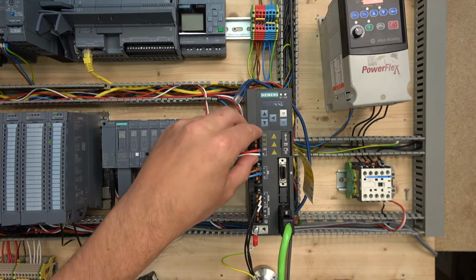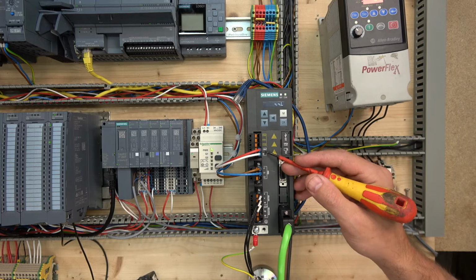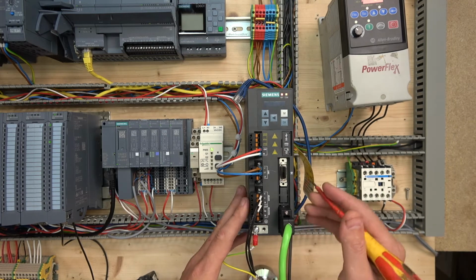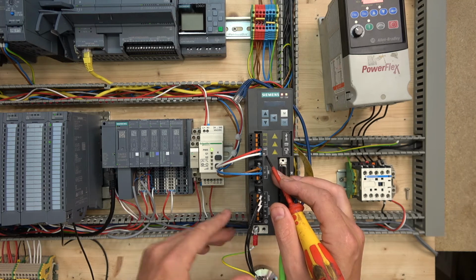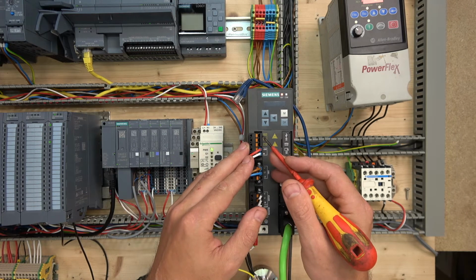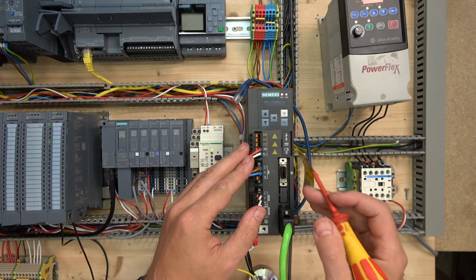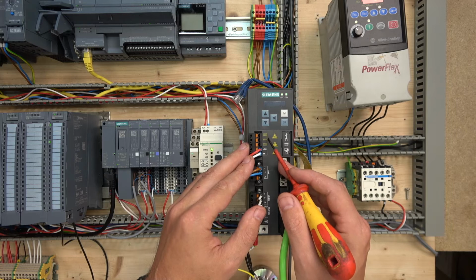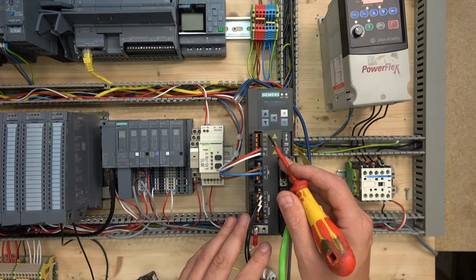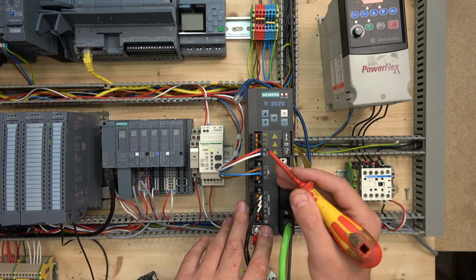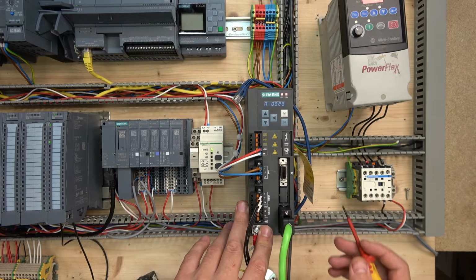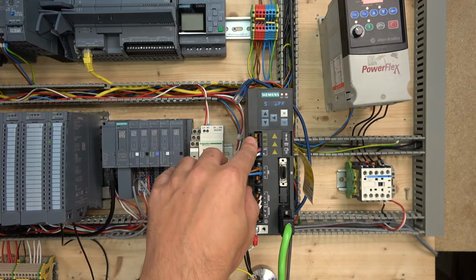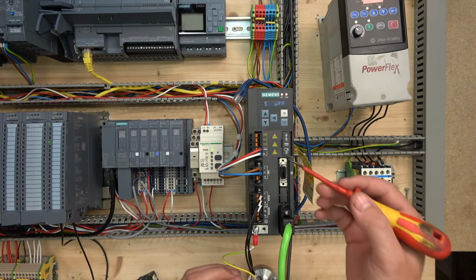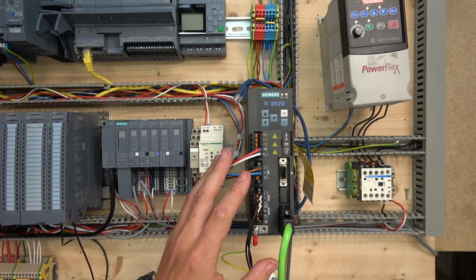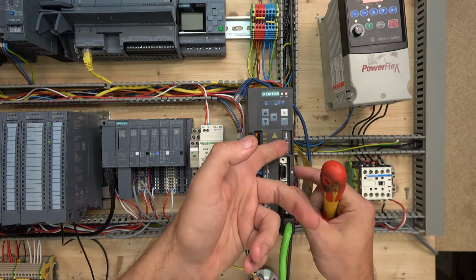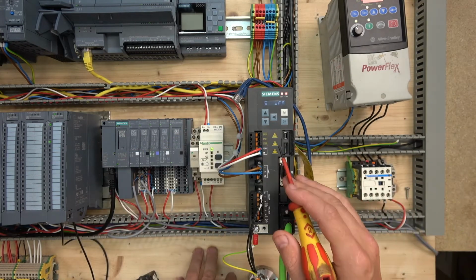From there on, we plug that on. We have a 24 volt supply for the controls, and as you can see, the drive has come on. It's 24 plus and minus coming from the DC power supply. Also, we have a link in here which links out STO, safe torque off, something like that. Basically, if these are open, and some cables are going to it and they're open, the drive will not run. So if you are using these, and you have a problem and the drive doesn't run, the first thing to check is to make sure that's there. After that, you have a little connector port in here where you have a USB connection.